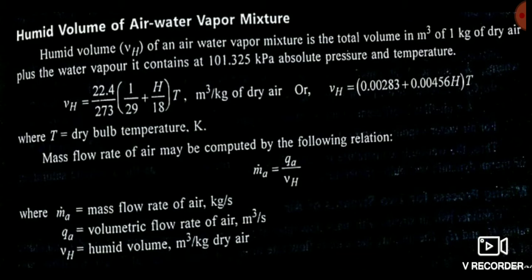Now see humid volume. The humid volume of an air-water vapor mixture is the total volume of 1 kg of dry air plus the water vapor it contains at 1 atmosphere (101.325 kPa) at absolute temperature. There are two formulas, both giving the same value. One is written in terms of fractions: VH = (22.4/273) × (1/29 + H/18) × T.